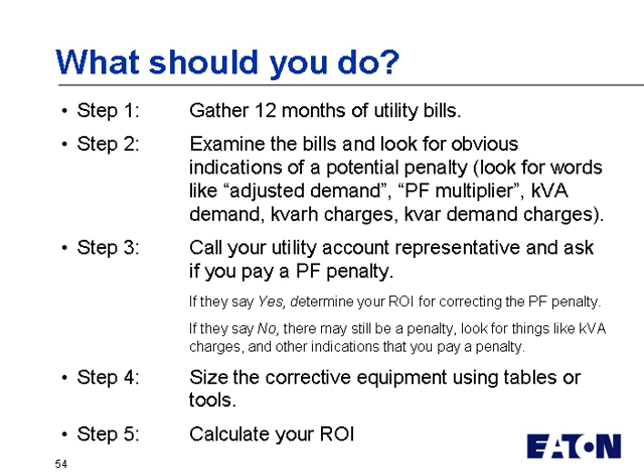A third step might be to actually call your account rep and ask if you pay a penalty. And they may say yes, and if they do, then you should really consider, well, what am I paying per year? And if they say no, it may mean that you don't pay a penalty, but it also may mean that you do pay a penalty, and they either don't know, and the rates may have changed, or they don't actually associate things like kVA rates with poor power factor.